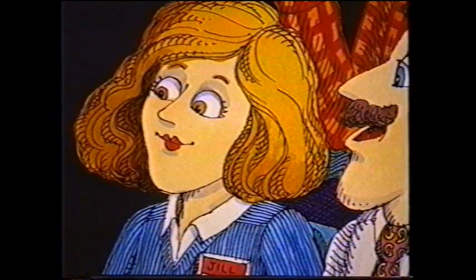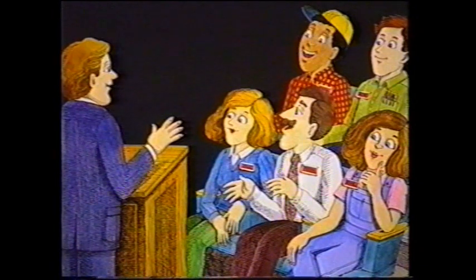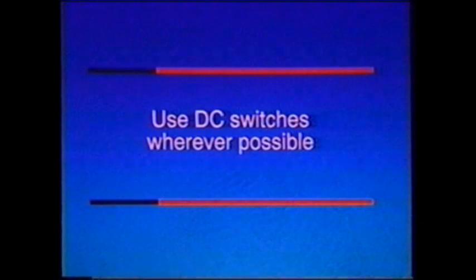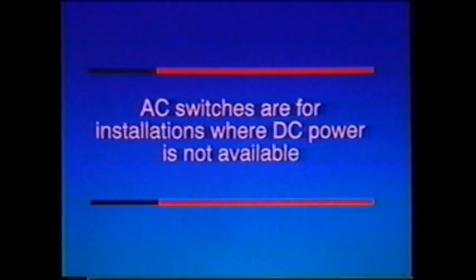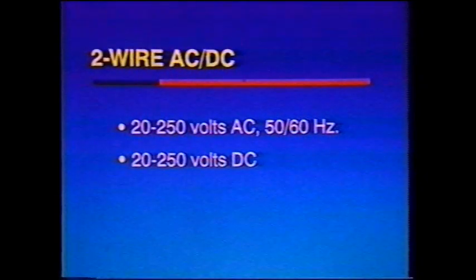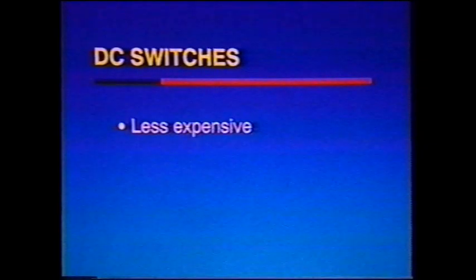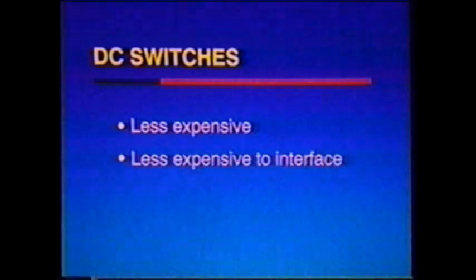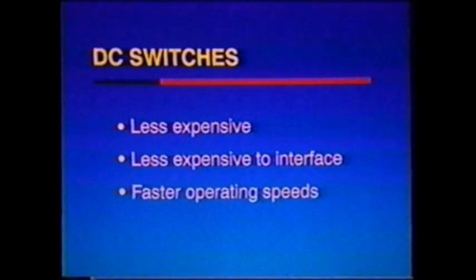If DC switches have all these advantages, why use an AC unit? If you have a choice, you normally will want to choose DC switches. But many installations don't have DC available, and that's where AC switches come in. A lot of plants have a mix of AC and DC applications — here you may want to consider AC-DC proximity switches. These units will typically operate from any power supply from 20 to 250 volts AC and 20 to 250 volts DC. To summarize, when you have a choice between AC and DC, DC switches are less expensive, less expensive to interface, and give you faster operating speeds.